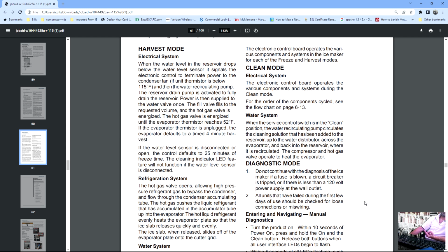Yes, but the older ones will not, because they use the evaporator thermistor to know how thick the ice is and when to harvest. So on the older ones, it's definitely not going to function properly, or at all, if the thermistor is disconnected. On this one, if you disconnect it and it can't see it, it's just going to override it and cause the ice to drop at 25 minute intervals. But does that mean the ice thickness might not be right? The customer might call you out and say, "Hey, listen, my ice thickness may not be right." How would we approach that?